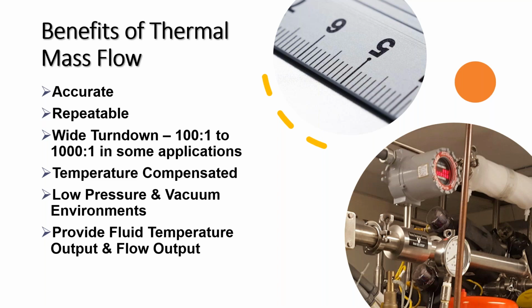The other nice thing about thermal mass is the wide turn down. Turn down typically means how wide of a flow range can you see. If you've got a flow range that's, for example, 0 to 100 SCFM, or 0 to 100 GPM of water, we pretty much, in most cases, can show you 1 SCFM, and at the same time, we can show you 100 SCFM. We can measure both ends of that spectrum. Some other technologies may not be able to do that. So that's why it's good to talk with your salesperson and know your application and know what you need to see and measure.